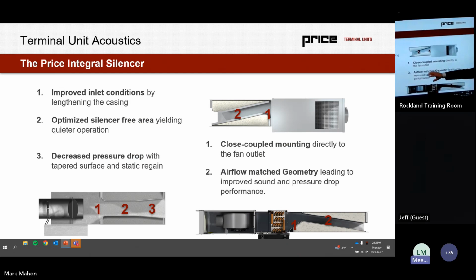It's all construction based. We do lengthen the distance a little bit between the silencer baffles and the inlet. We play with that a little bit in our design. So we cut a little off the inlet. We move the nosing of the silencer a little deeper into the actual silencer casing. That helps with creating some normalized airflow velocity. More importantly, we optimize the silencer free area for every unit. So essentially we tune the silencer to the valve size.